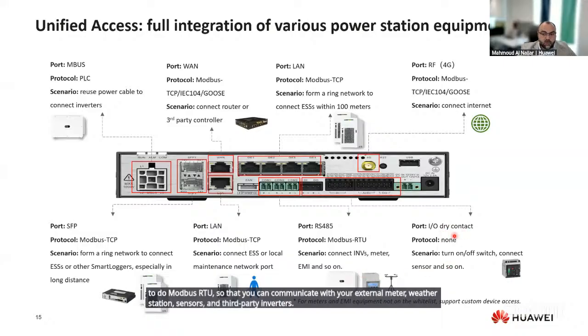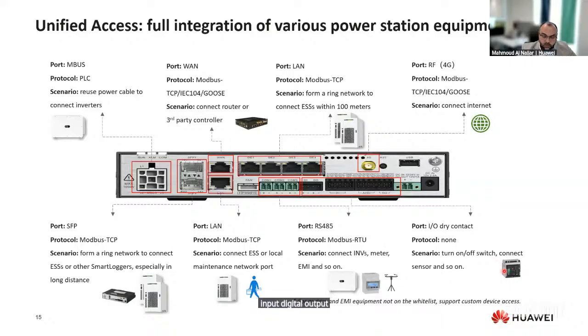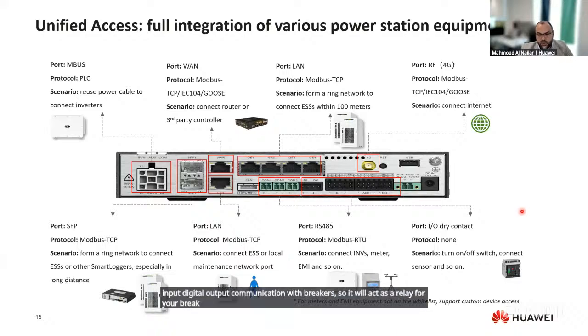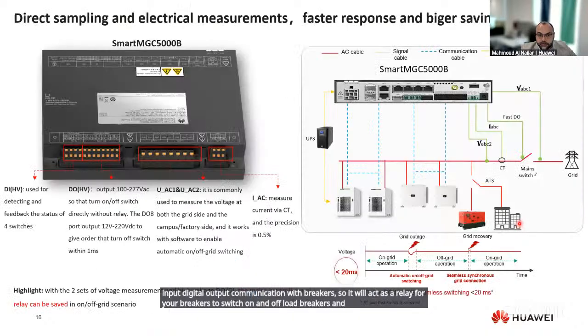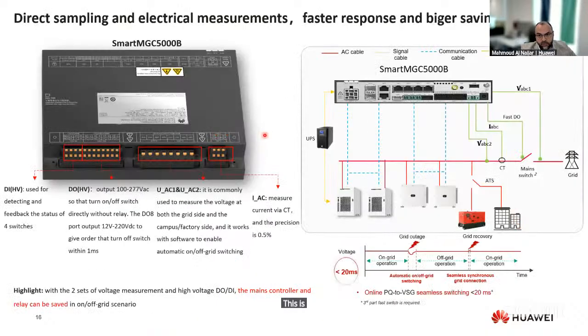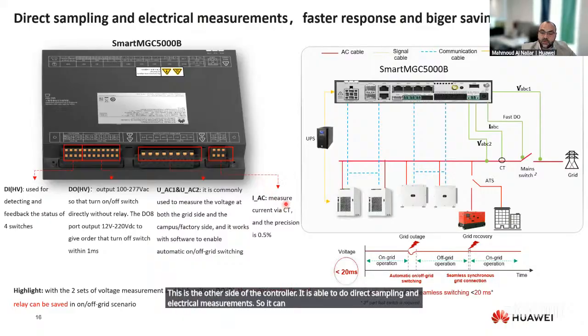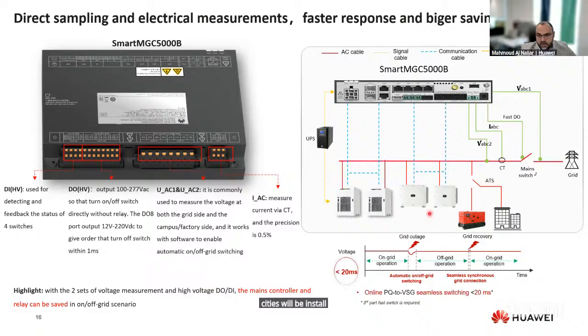It also has the capability to do DIDO, dry contact, digital input, digital output communication with the breakers. So it will act as a relay for your breakers to switch on and off load breakers and controllers. This is the other side of the controller. It is able to do direct sampling and electrical measurements. So it can directly measure the current from the CTs. As I said, this is an AC coupled system, so CTs will be installed to measure the load.